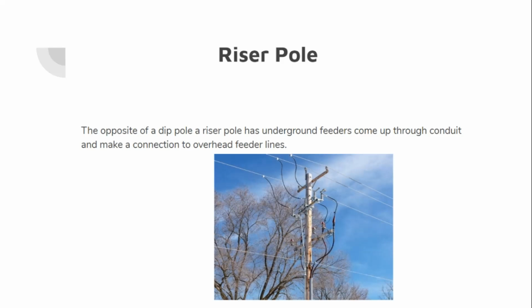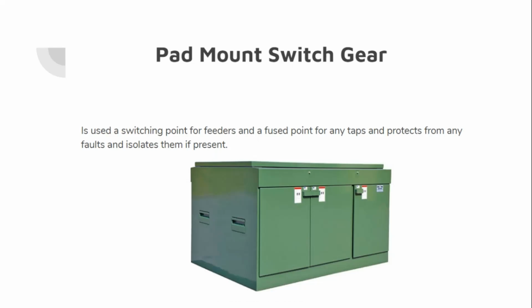Overhead. Feed direction is from underground to overhead. That is a riser pole. Pad mount switchgear. A pad mount switchgear is used as a switching point for feeders, 100% correct, and a fuse point for any taps and protects from any faults and isolates them if present. Very good description.